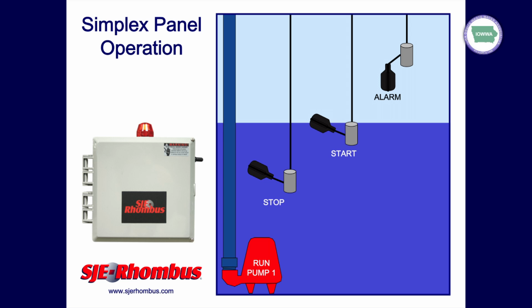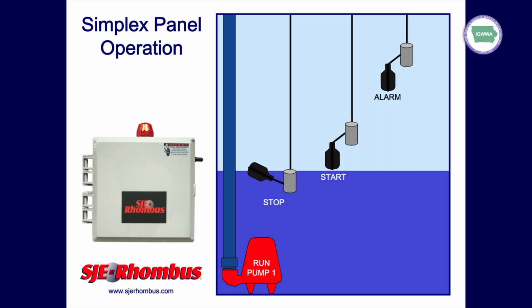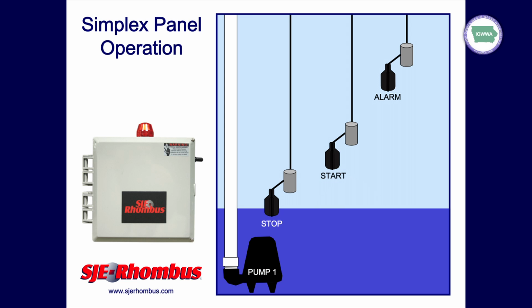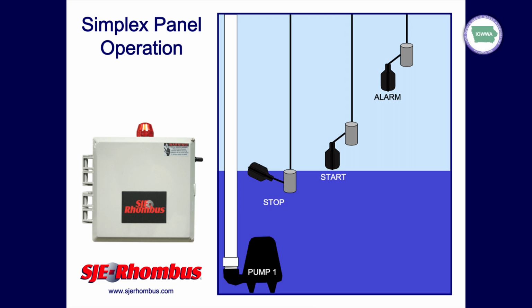Normal operation, when that start float drops out, nothing's going to happen. We've got a holding relay in the panel that's going to keep the pump running until we reach the stop point. And then at that point, we'll interrupt power to the pump and shut everything down. So we can control what the pump operating range is by separating the distance between our stop and our start float, limited only by the depth of the tank. You know, the deeper the tank, the greater that operating range can be.